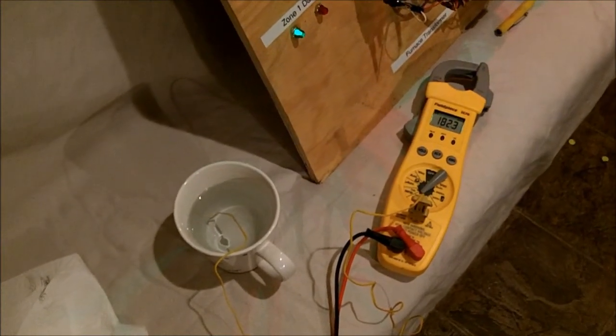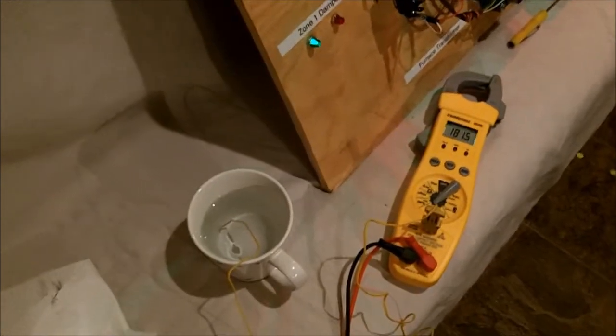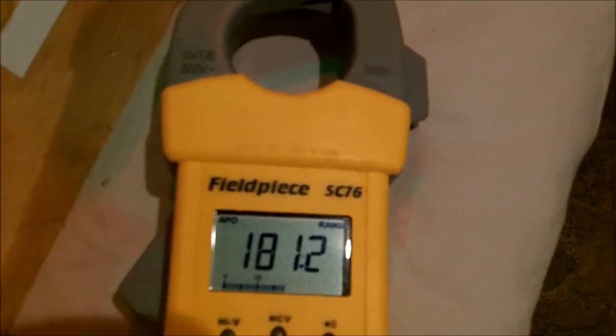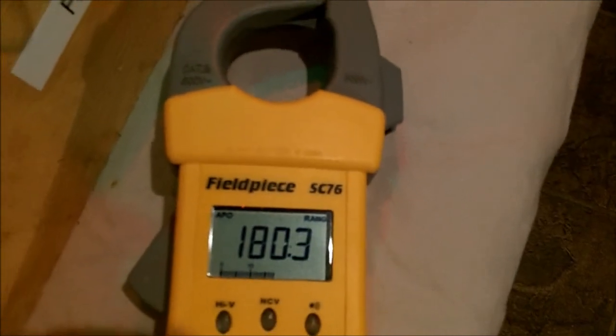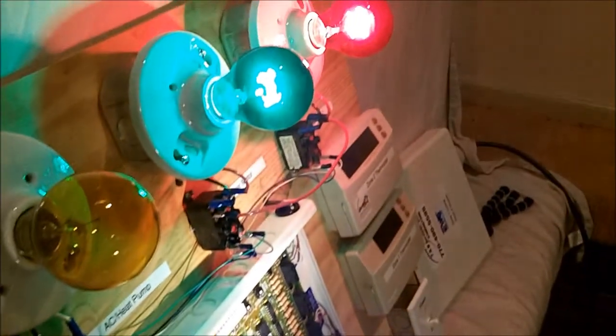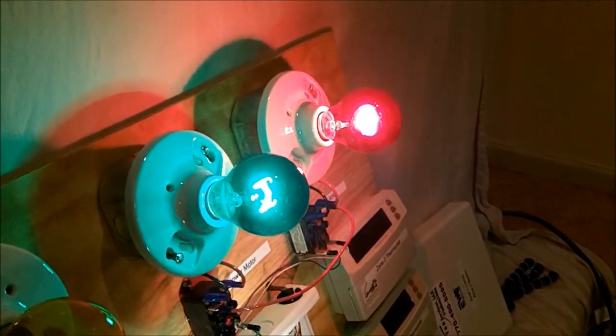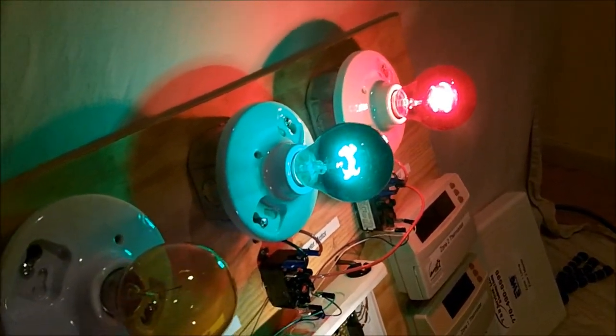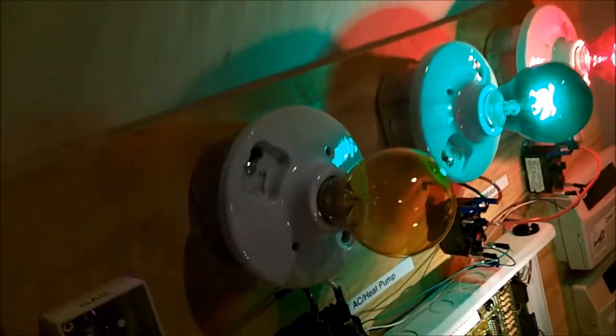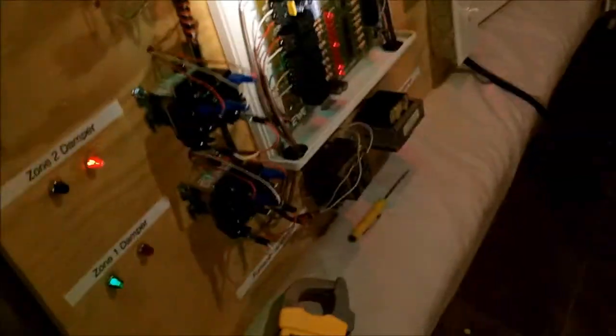Okay, now what we're going to talk about is the supply air sensor. I've got a cup of hot water, and I've got my thermocouple from my thermometer, and you can see it's 181 degrees. So right now the furnace and the blower is on. So what I'm going to do is stick that supply air sensor in that cup of hot water. Well, it's gone down to 179 degrees now. But I'm going to stick that supply air sensor in the cup of hot water and wait for the furnace to cycle off.